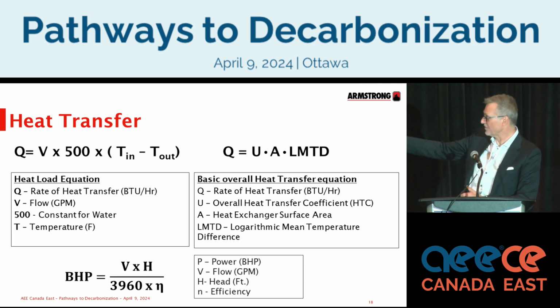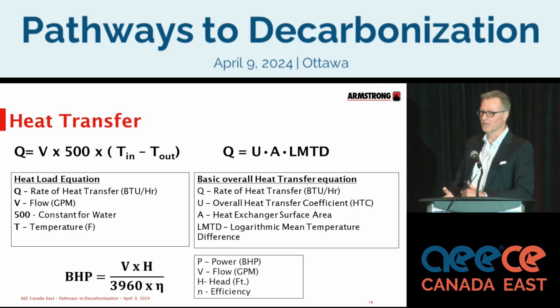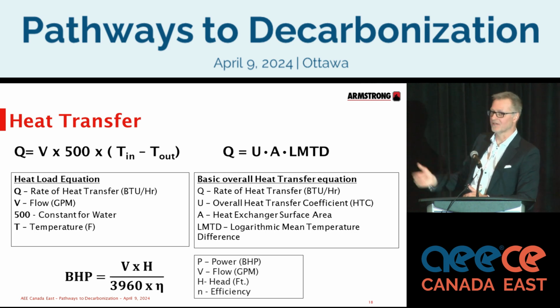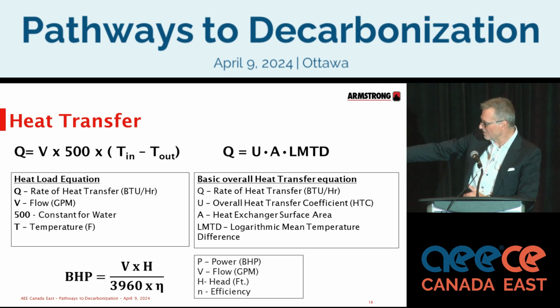Now, if you increase or decrease that temperature approach, your LMTD, you're trying to move more energy from one side to another. What does that affect? The surface area. What happened at Toronto Western? Less temperature, more surface area. But at the same time, if you look at the bottom equation, which is the simple pump equation, the brake horsepower required by a pump is equal to the flow times the head divided by 3960 times the efficiency.